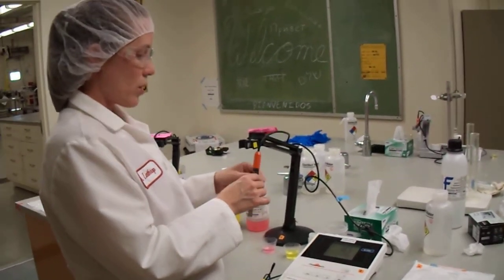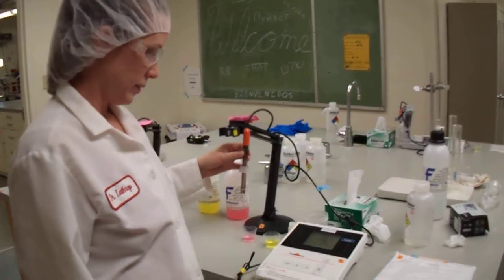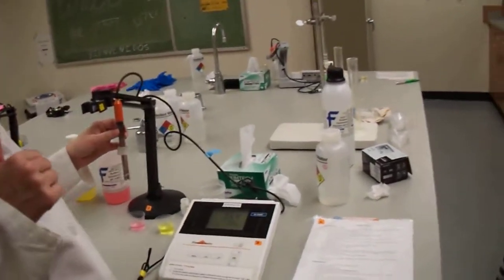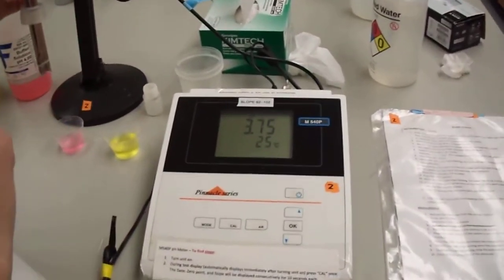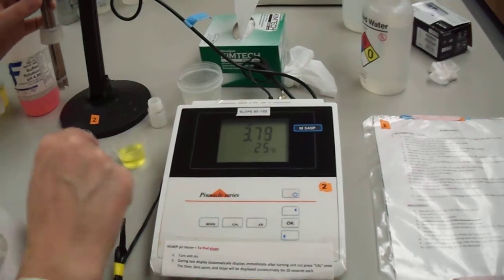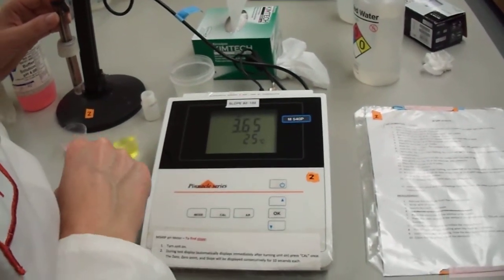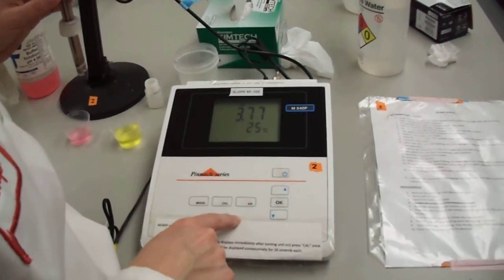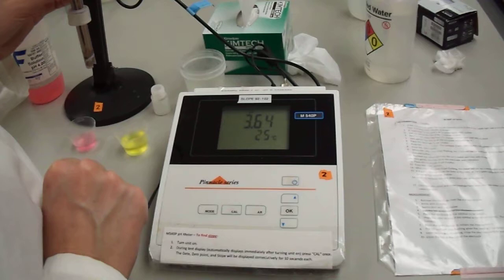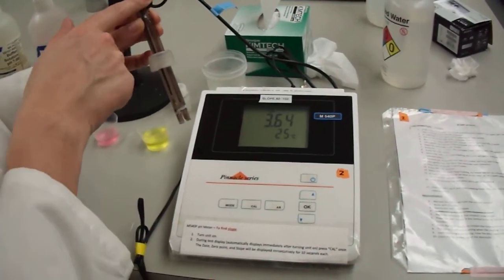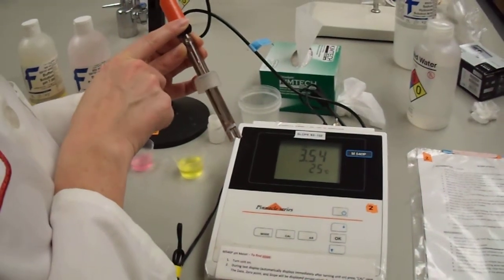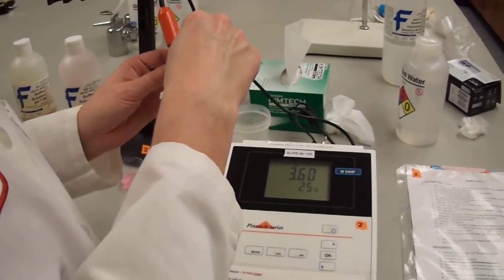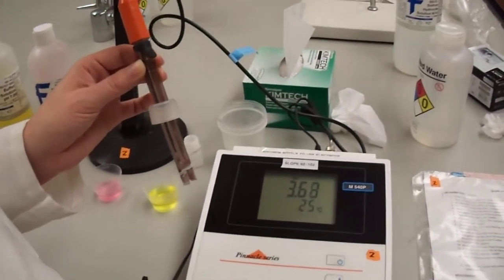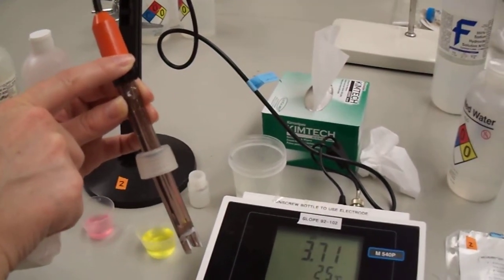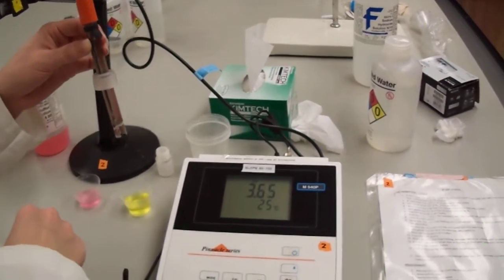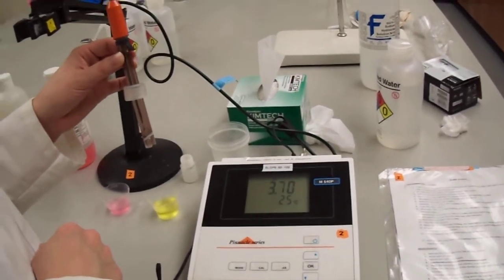So what are the first things that I need to do, friend? If the meter is turned off, you need to press the on and off button, which is found on the upper right side of the meter. Okay, so we're already on. Also, if the auto read is on, turn it off by pressing the AR button next to the calibration button. Okay, so we would see an AR symbol up here, but it's not on. Next, as you've already done, pull the tab at the top of the electrode to open. You can see there's a little hole there, and it needs to be open in order for the reading to be read properly. Also, as you've already done, the electrode will be removed from the storage solution and rinsed with DI water, and then blotted gently with a Kim wipe.